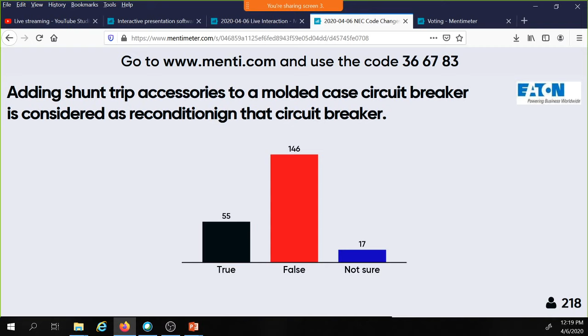The key thing to remember when working with molded case circuit breakers: if you're adding accessories per the manufacturer's instructions, that device was designed for what you are doing. So when following manufacturer instructions, you may need to take a portion or the entire front cover off the circuit breaker. Those do not have a seal on the outside, so you can do that. You can install shunt trip and other accessory components because that is part of the listing, and that is not considered reconditioning.